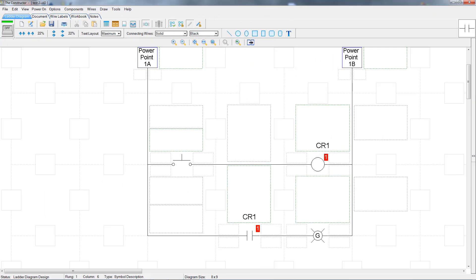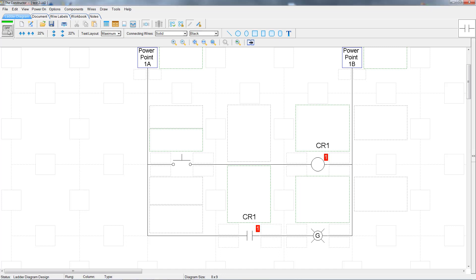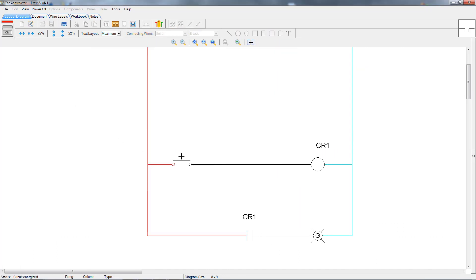Let's do one more small example to help clarify defective modes. This example will also be with the project mode set as normal. In this simple circuit, we have one relay controlled by a normally open push button. The relay has one normally open contact that controls an indicator light. When we push on the push button, the CR1 relay energizes and its contacts close, which energizes the indicator.